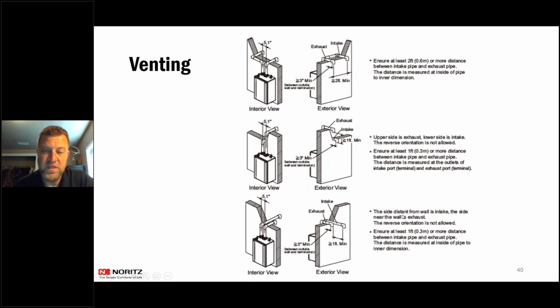Most of the installs that we see, they're coming out right next to each other. The intake is dropping straight down, and then they're snorkeling the exhaust up 12 inches and 90 and out. So you have that 12-inch separation from the exhaust and the intake. So there's a bunch of different ways that you can do that. If you are coming in on that same plane at the same height, that exhaust and that intake need to be at least 2 feet away.